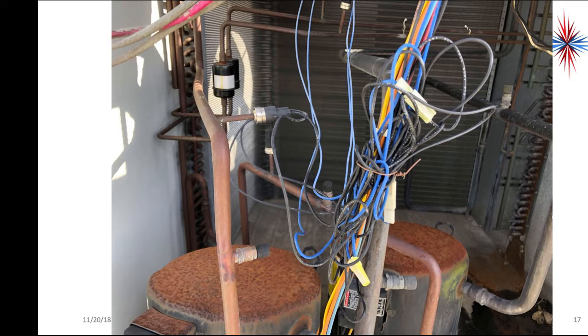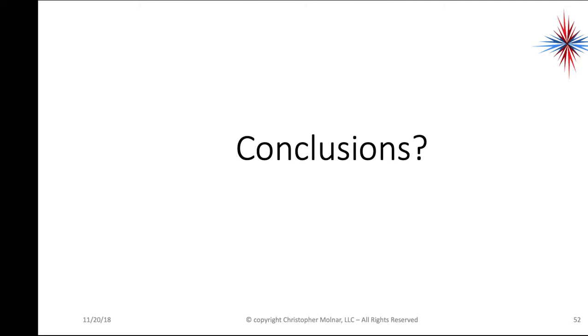What I found out was that the low pressure switch was actually bypassed and no longer in the circuit. So when that compressor lost charge and Y1 and Y2 were jumped out on the control board, that compressor continued to run. From our conversations before, we know that refrigerant is part of what cools the compressor. So what I found here, and it's up to others to totally make the conclusions, was a bypassed high limit switch and a bypassed low pressure switch left the compressor running dry, basically with no refrigerant to cool it. There was a leak in the evaporator coil which was caused by improper maintenance, and the smoke that people smelled was the fan motor belt burning up because it also was not properly maintained.